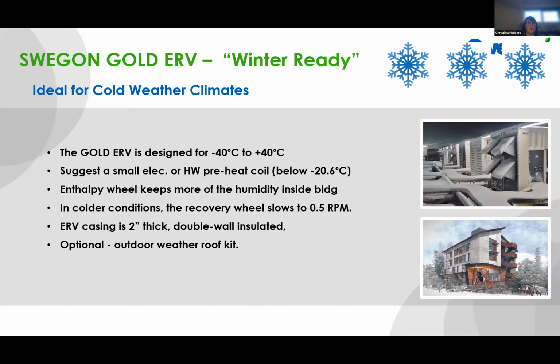I wanted to show you how it works in our cold climates in Alberta. The Swegon Gold ERV is designed for temperatures of -40 to +40. We do suggest a small electric or hot water preheat coil below -20 degrees C. But in colder conditions, if there is any frost buildup on the wheel, the enthalpy wheel will slow to a speed of 0.5 RPM using a stepper motor on the wheel. It gives the wheel longer in the warm airstream to remove any frost on it, and then it will continue operation. This is all automated into the unit, so it'll sense the outdoor air temperatures and continue.